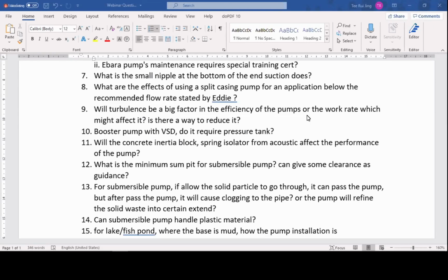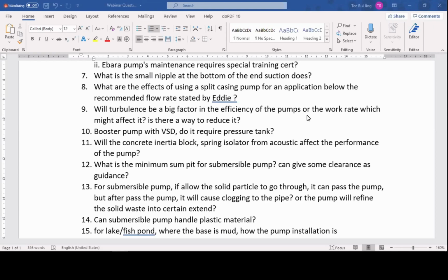Okay, number 9. Will turbulence be a big factor in the efficiency of the pumps or the work rate, which might affect it? Very, very technical question. Yes, turbulence will affect the suction of the pump. Now, one of the main causes of turbulence is the way the suction pipe is designed into the pump. For example, if you have an elbow right before the pump inlet, this can cause turbulence when water actually enters into the pump.